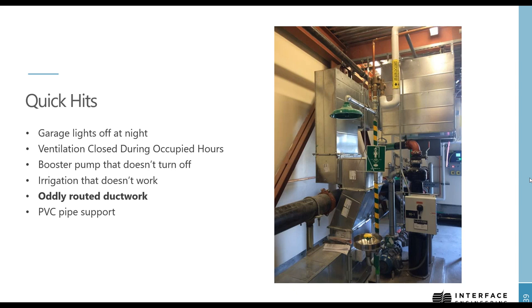Now, this is a life safety system that when there is a refrigerant leak, this kicks on in full to exhaust the air and make this space safe for someone who might be in there. But in this case, because of this routing of the ductwork, they were not able to meet the design requirements of this fan and therefore would not have been able to safely exhaust air from this space in case of an emergency. Now, hopefully this is a type of system that will never operate, and especially not with someone in the room when it happens. But this is not the type of system that we want to find out doesn't work correctly when that emergency does happen.